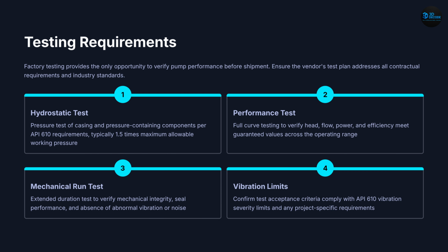Slide 14. Testing requirements. Ensure vendor performs hydro test, performance test, and mechanical run test. Verify vibration limits and acceptance criteria.